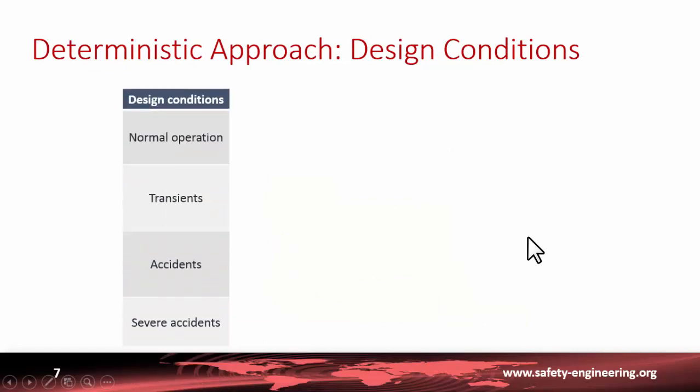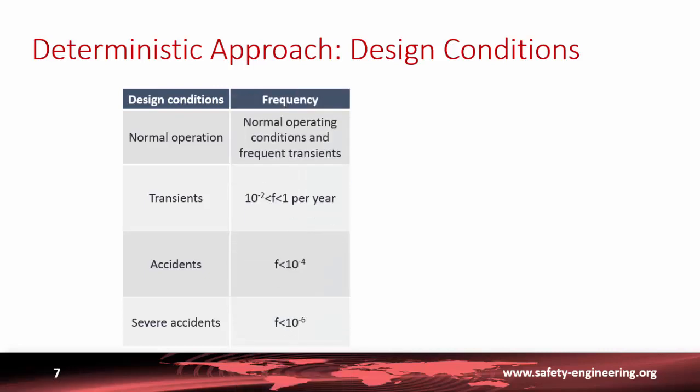This is the way we define what we call the design conditions, which include normal operation, transients, accidents, and severe accidents. Normal operation is something that happens permanently or includes frequent transients. Transients could happen once a year or once in a century. Accidents should have a probability less than 10 to the minus 4, that is one every 10,000 years. For severe accidents, the objective is to have a frequency less than one in a million years.